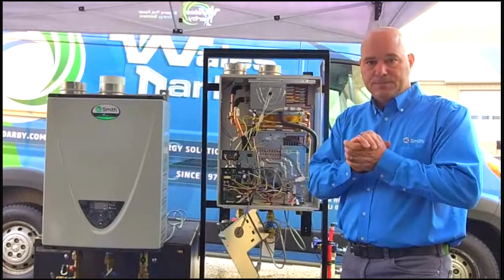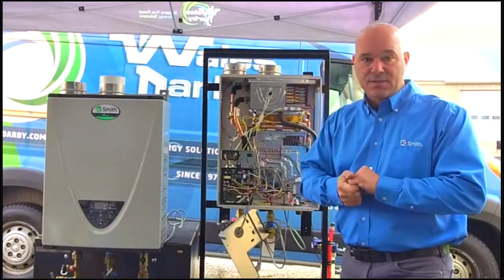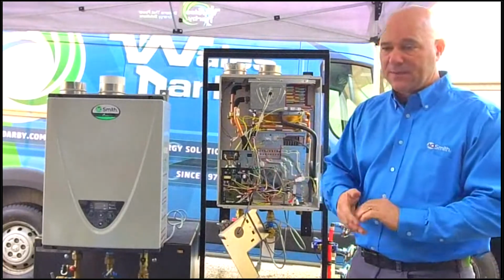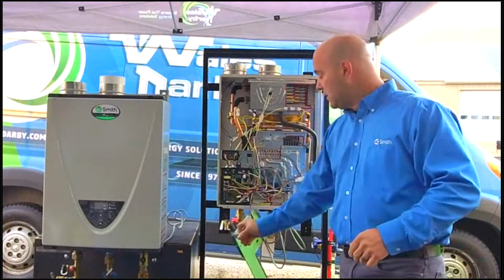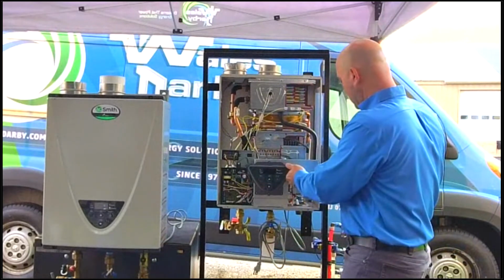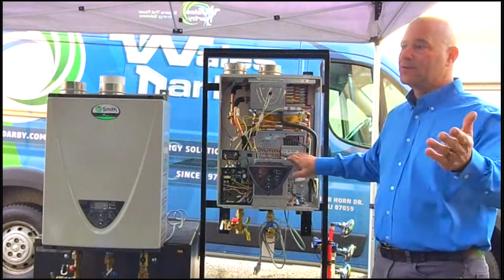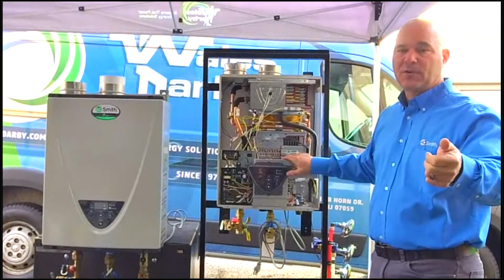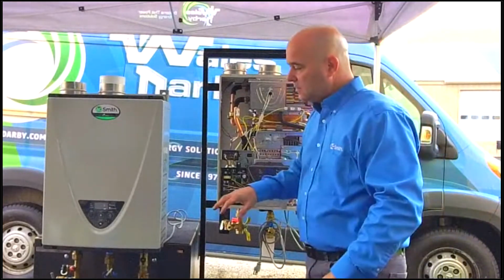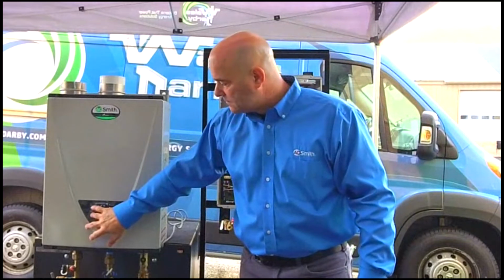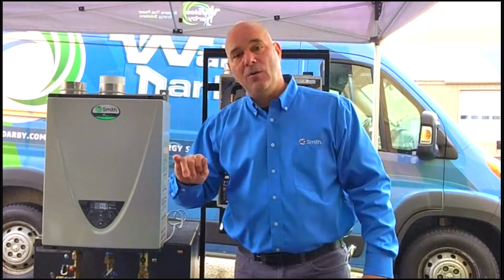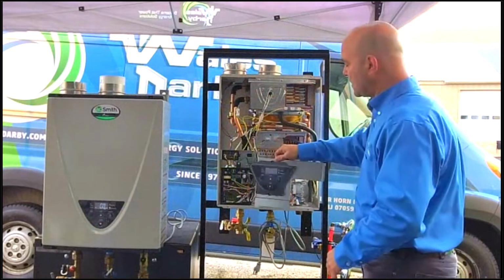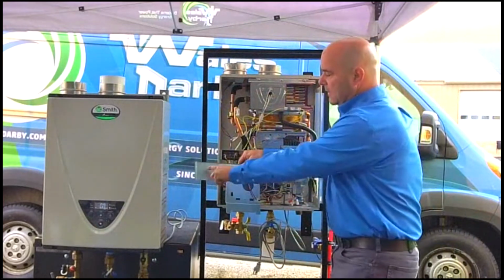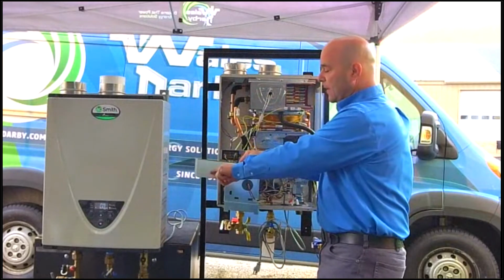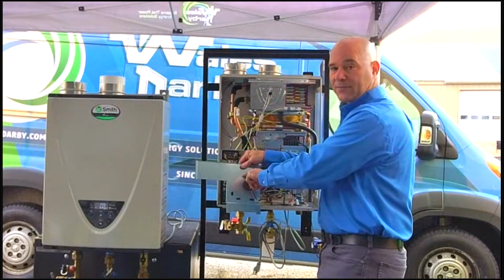You just do an install and you want to know how this thing is going to perform. What I like to do, and we always recommend to our guys that are installing these, is you take the control that's normally in this position and you go somewhere in the home, usually a bathtub or something, and you open it up to full capacity. And you put your unit and you monitor the flow. And that flow is going to tell you, brand new unit, this is my flow rate. What we recommend is you take this control, flip it backwards, and on here you put the date it was installed, you put the flow rate and where you took that flow rate, downstairs bathroom tub.